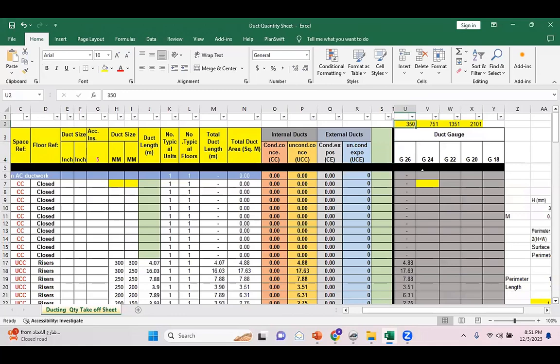If any size of the duct, height or width, is less than 350, it comes to 26 gauge. If it's more than 350 but less than 750, it will be 24 gauge. If it's more than 750 but less than 1350, it will come into 22 gauge.